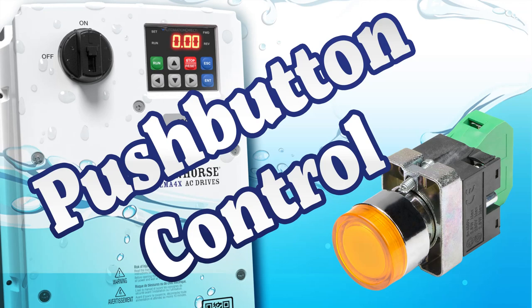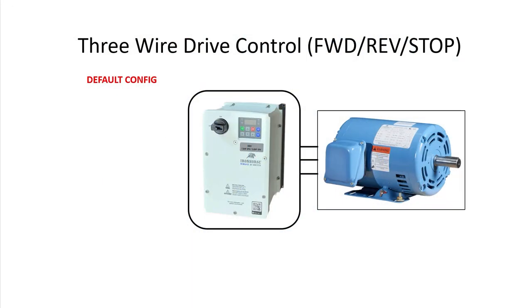3-wire control is super easy to set up. The default drive is configured for 2-wire operation using maintained selector switches and it's wired like this.